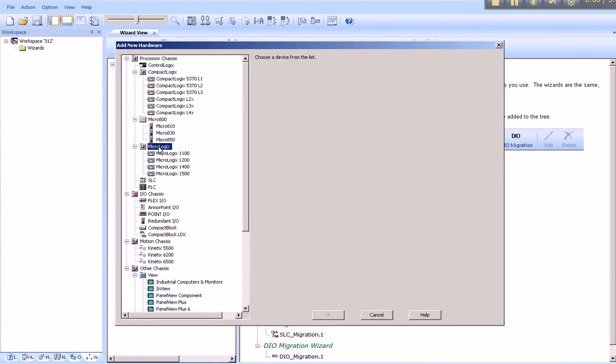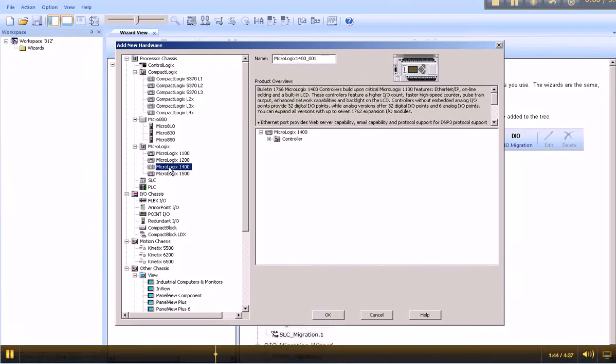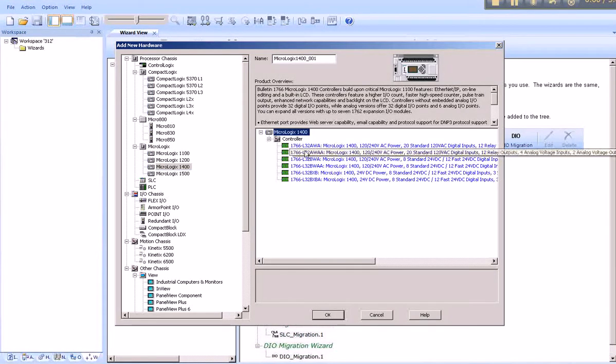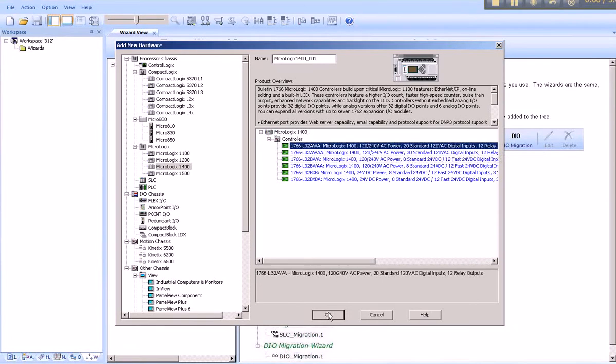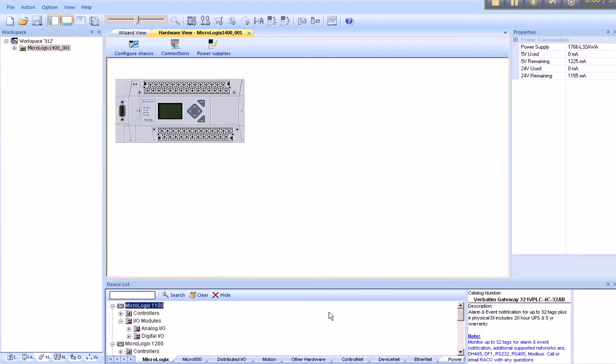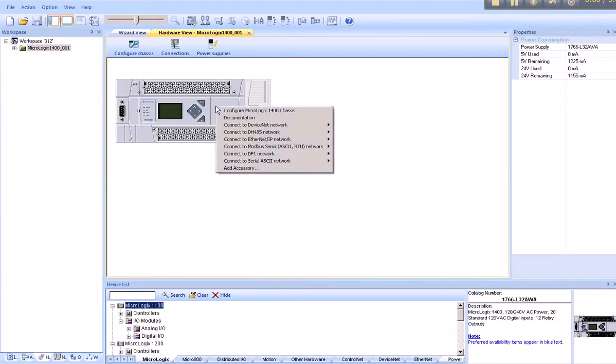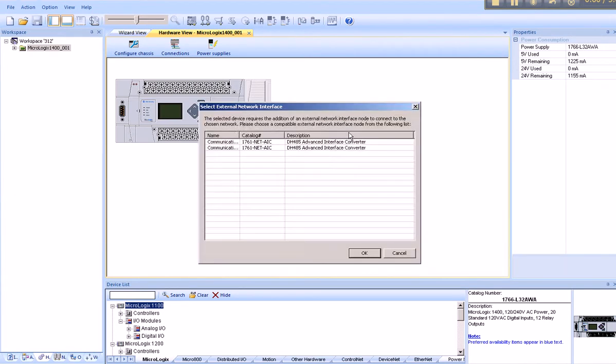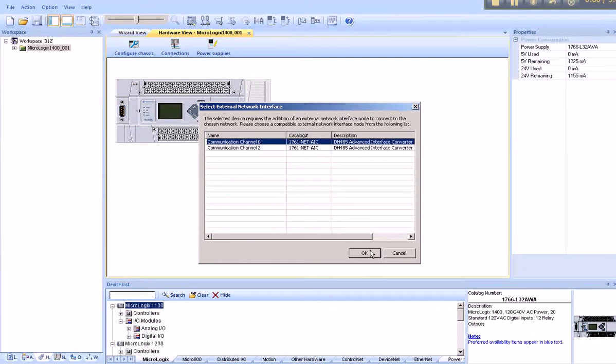Under MicroLogix, there are four different platforms. We scroll down to 1400 in this example. Any processor will do. Once the processor is on the screen, we right click, scroll down to DH-485. Our only option is to connect using an external device. In this particular case, we will utilize 1761 NetAIC and we communicate on Channel 0.